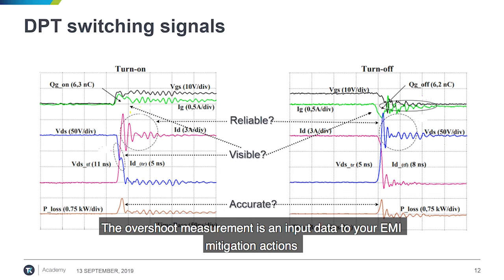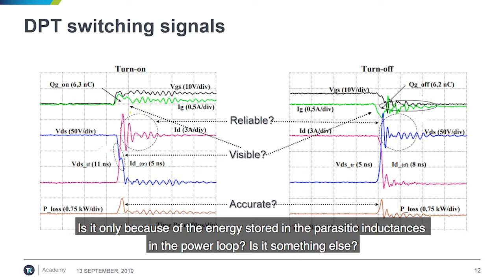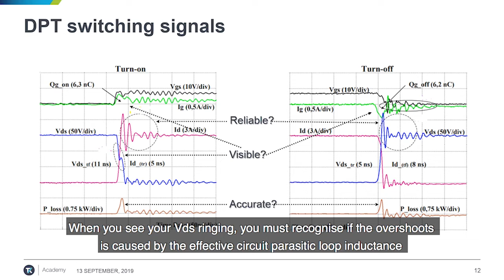So all these measurements are really important, and you need to know if you need to apply some clamping—maybe you have to redesign something. Is this ringing only because of the energy stored in the parasitic inductances in the power loop, or is it something else? When you see the ringing, you must recognize whether the overshoot is caused by the effective circuit parasitic loop inductance, or estimate a contribution from the measurement system itself.